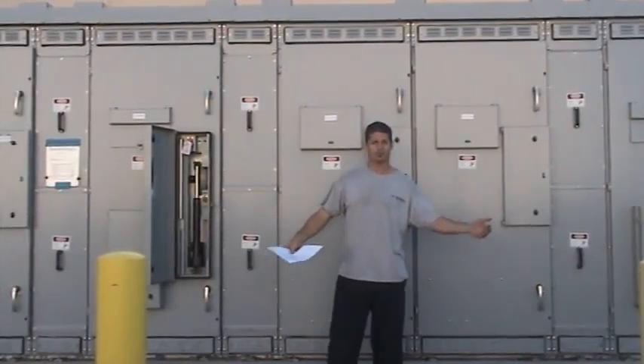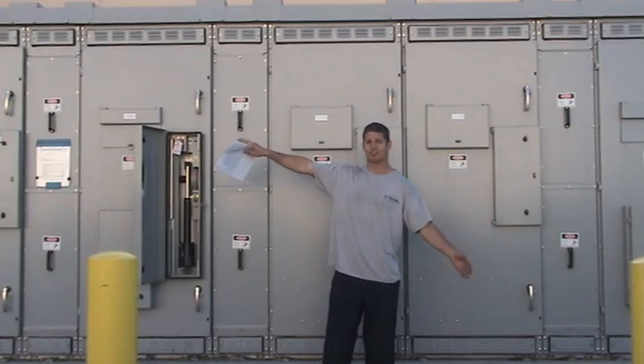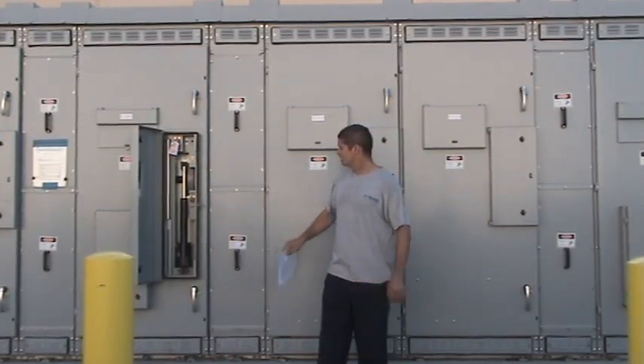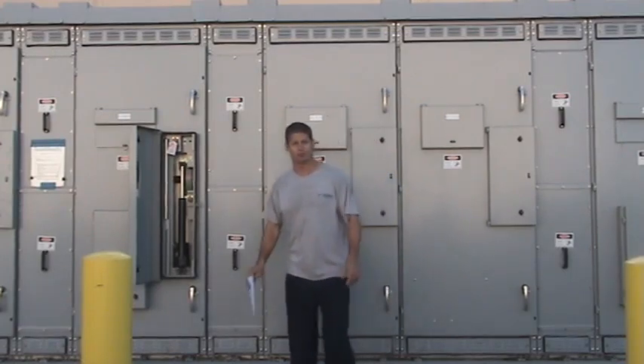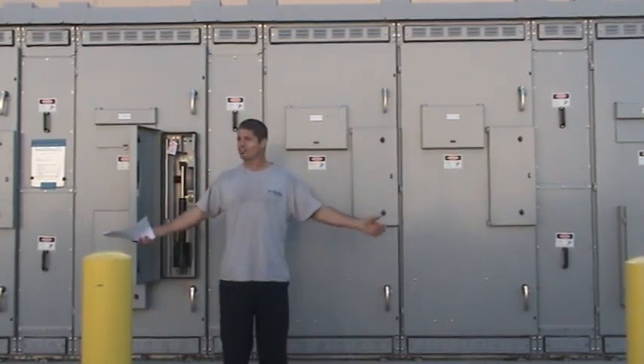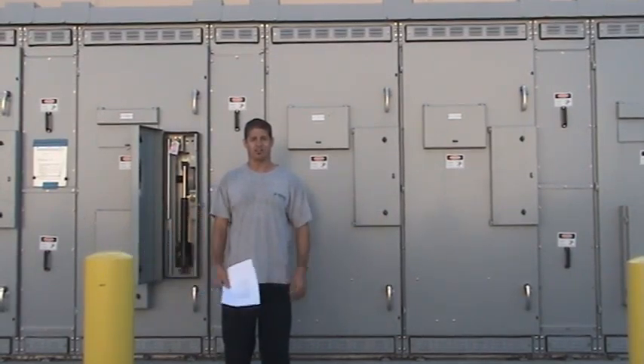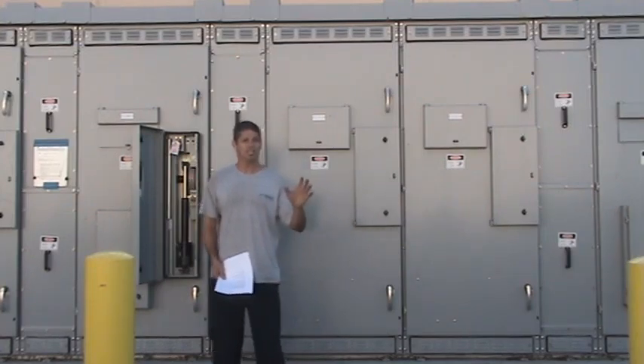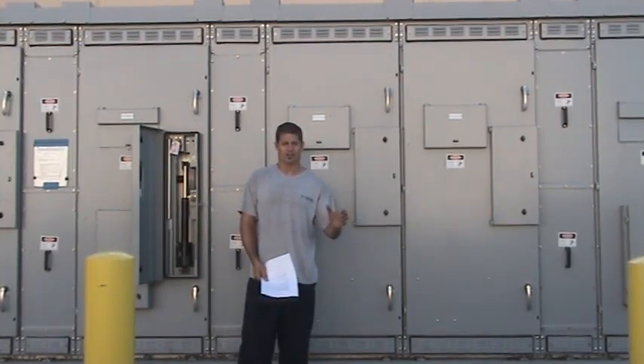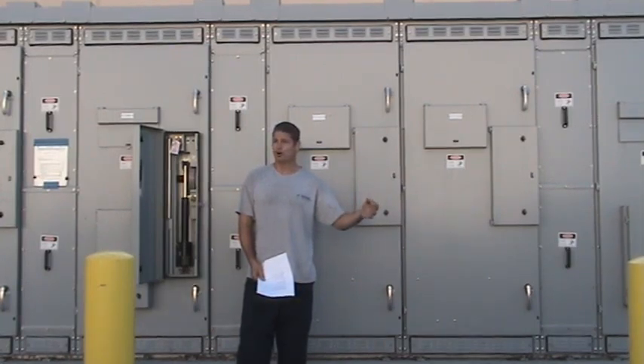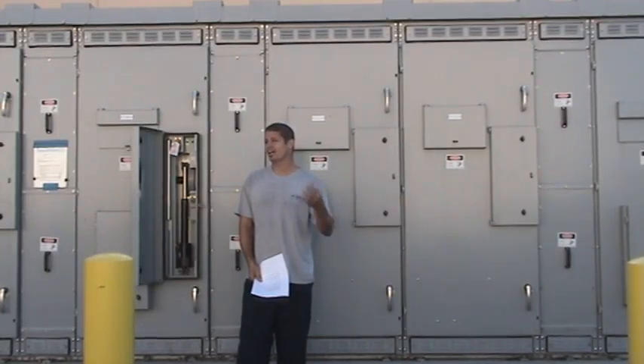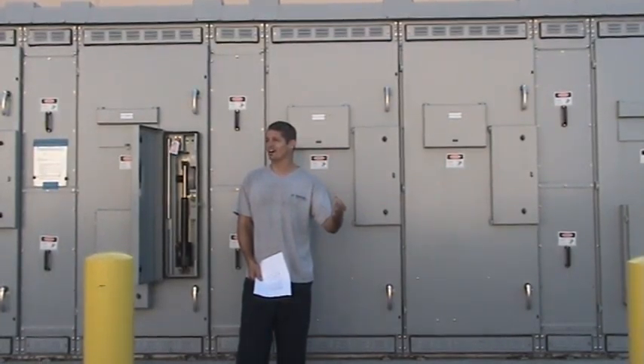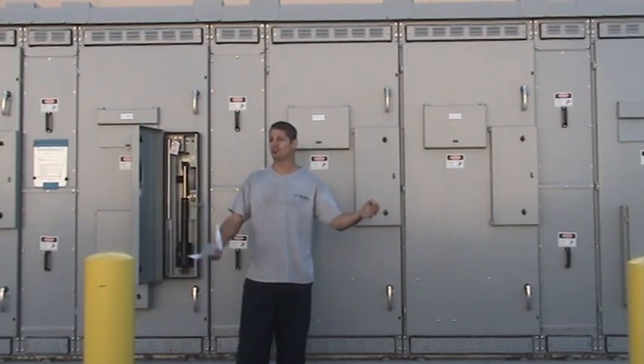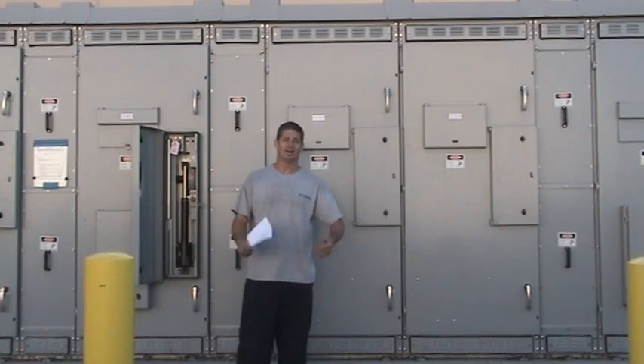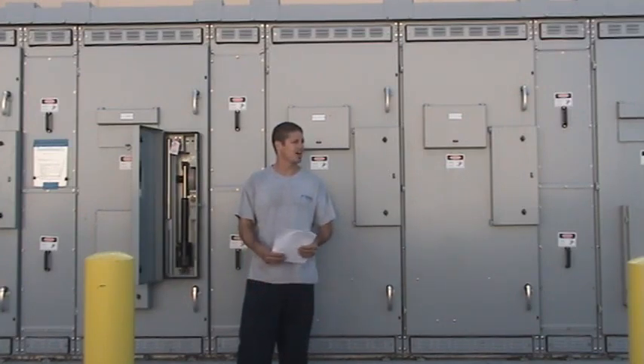And again, to reiterate, let's say you need to do something with the generator down line, or some of the gear needs to be fixed, then you'd flip into manual, right? Maintenance. There isn't really that much maintenance on this thing, guys. The only thing the O&M really calls out is the cleaning of the 12 kV connections and bus. That's just a standard deal with 12 kV or any type of high voltage. You try to keep it as clean as possible. That's going to be up to you guys. It recommends certain things for maintenance in the O&Ms, which will be provided to you.